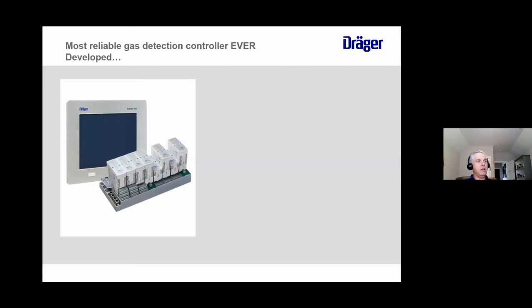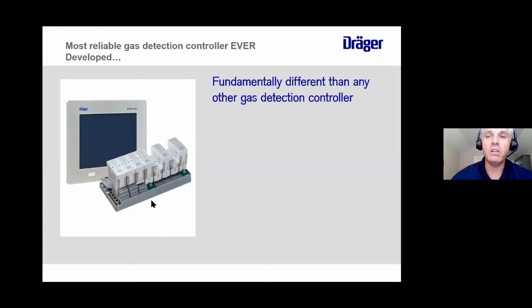So, like I mentioned, it's by far the most reliable gas detection controller ever developed, and the main reason why is it's fundamentally different gas detection control than anything else out there. The main reason is we have no single point of failure. That's a buzzword, a catchword all our sales guys need to be using when we're going out there talking about this thing. On your traditional controllers, you have basically a master board that controls all the functions of that controller. So if something happens to that board, you've lost your controller. When Draeger was developing this product, we said, we don't want that to happen. We don't want one single point that, if it fails, kills the whole system. So at Draeger, we developed a system with no single point of failure, right?